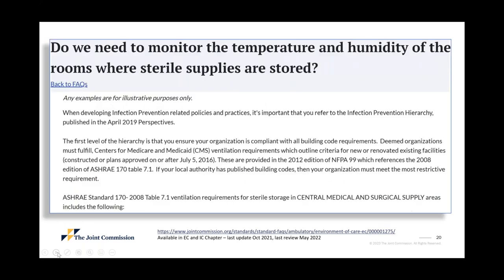We do try to provide direction by updating and providing frequently asked questions. Here's an example of something that often comes up during survey and is probably one of our most frequently asked questions: do we need to monitor the temperature and humidity in rooms where sterile supplies are stored? Well, the first thing we say is, first follow the hierarchy. Is there a regulation that requires a specific temperature and humidity in the areas where sterile supplies are stored? If so, our expectation would be that you follow that requirement - so if you have a building code requirement.